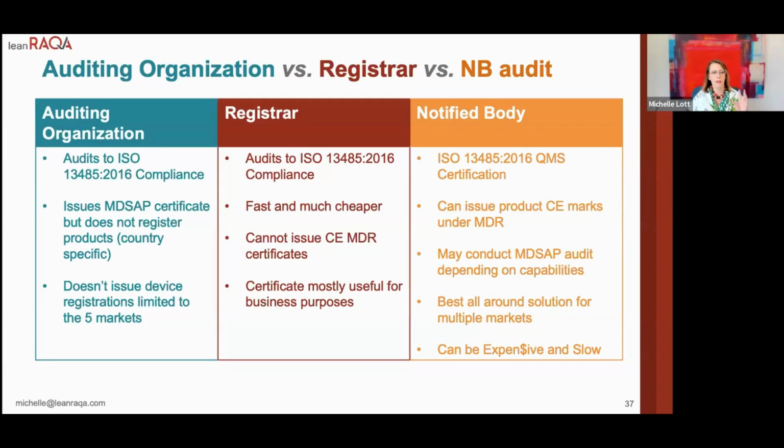They are designated by different bodies to conduct ISO 13485 compliance audits in the context of the MDSAP program. So MDSAP in and of itself does not register your products in the particular country. But again, if you're already selling or planning to sell into the country, you have to have it included in your MDSAP audit scope.